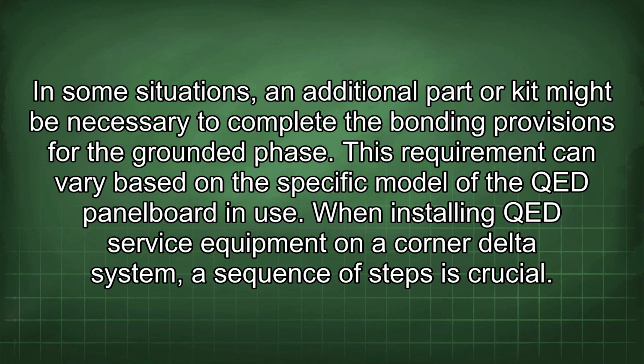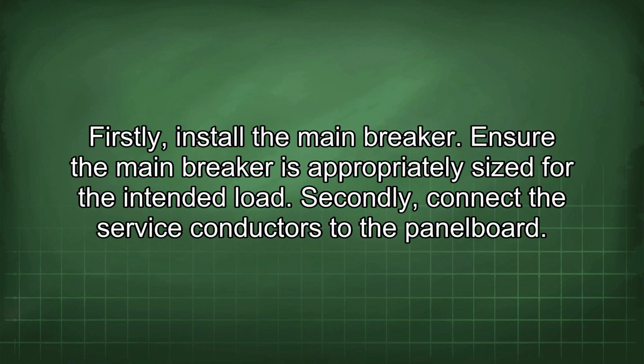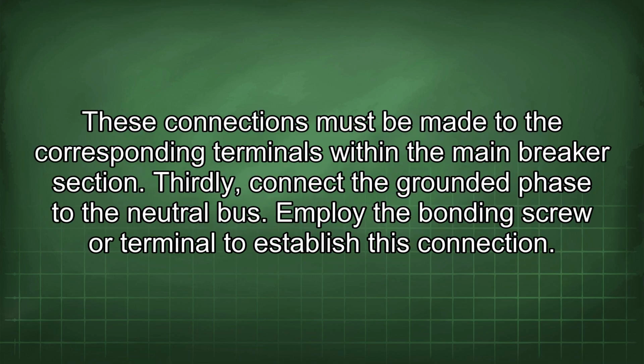When installing QED service equipment on a corner delta system, a sequence of steps is crucial. Firstly, install the main breaker. Ensure the main breaker is appropriately sized for the intended load. Secondly, connect the service conductors to the panel board. These connections must be made to the corresponding terminals within the main breaker section. Thirdly, connect the grounded phase to the neutral bus. Employ the bonding screw or terminal to establish this connection.